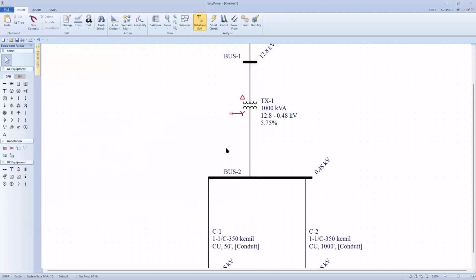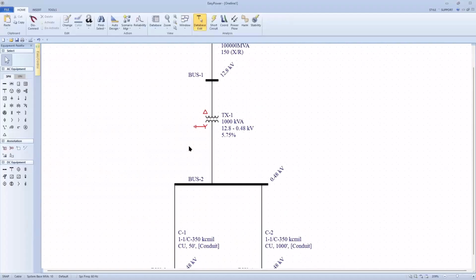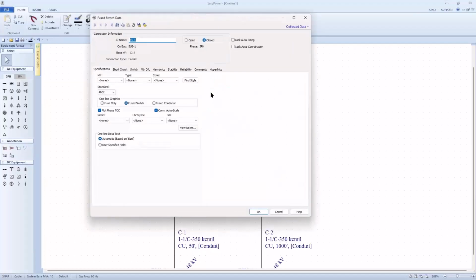Now, the reason I like this example as much as I do is that he said he had only one protective device in his system, and it was a fuse in the electrical cutout switch. So I'm going to pick up the fuse switch and insert it in the utility feed into my transformer. And then I need to find characteristics for the data sheet. EasyPower has a device library with over 40,000 entries in it. And I want to make sure the data sheet for this fuse is included in my model.